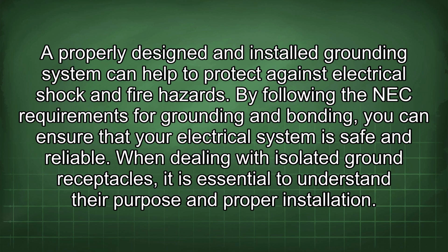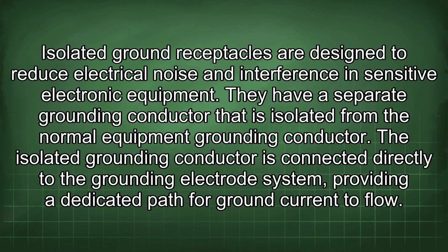When dealing with isolated ground receptacles, it is essential to understand their purpose and proper installation. Isolated ground receptacles are designed to reduce electrical noise and interference in sensitive electronic equipment. They have a separate grounding conductor that is isolated from the normal equipment grounding conductor. The isolated grounding conductor is connected directly to the grounding electrode system, providing a dedicated path for ground current to flow.